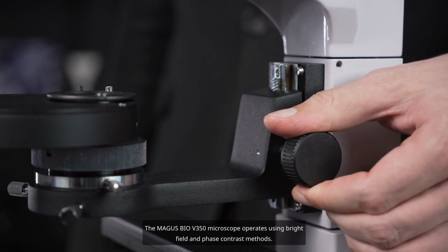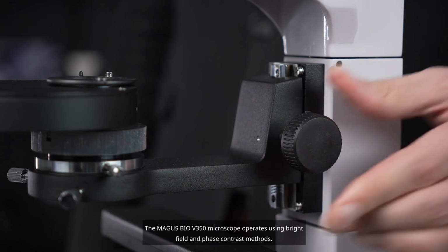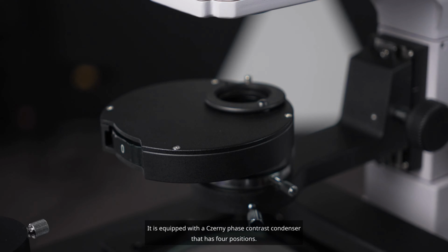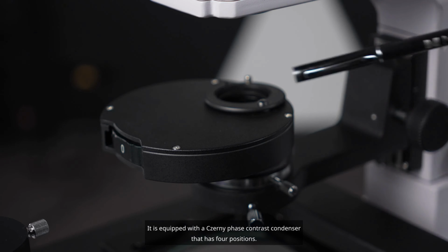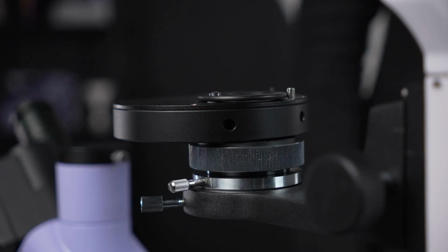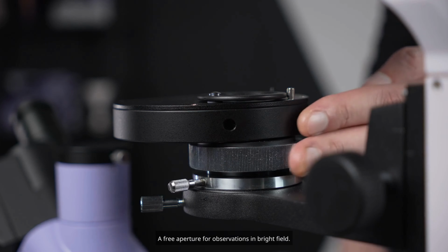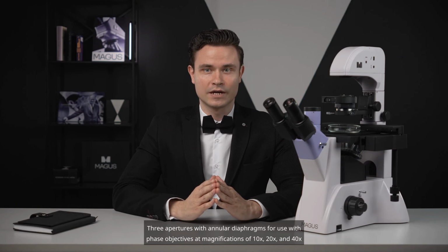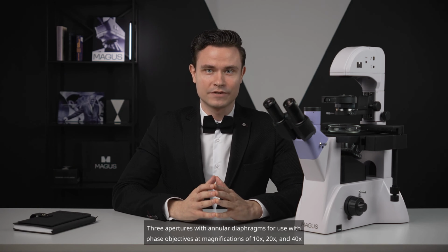The MAGUS Bio V350 microscope operates using bright field and phase contrast methods. It is equipped with a phase contrast condenser that has 4 positions: a free aperture for observations in bright field, and 3 apertures with annular diaphragms for use with phase objectives at magnifications of 10x, 20x, and 40x.